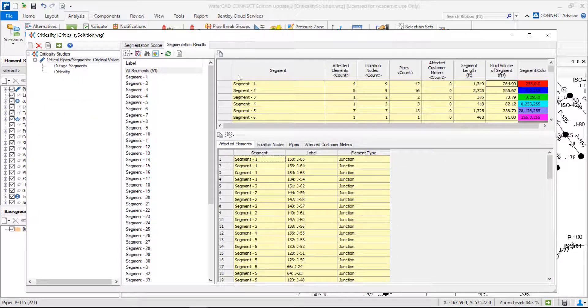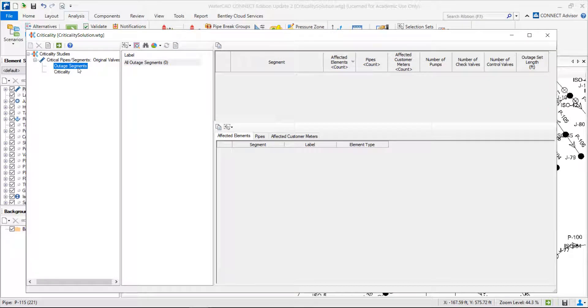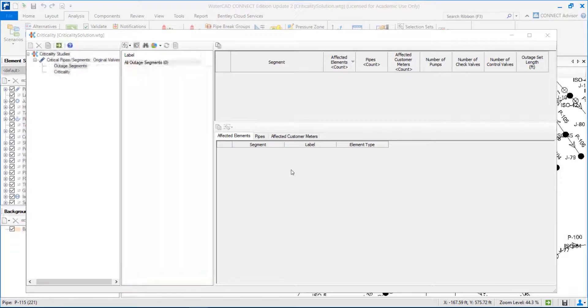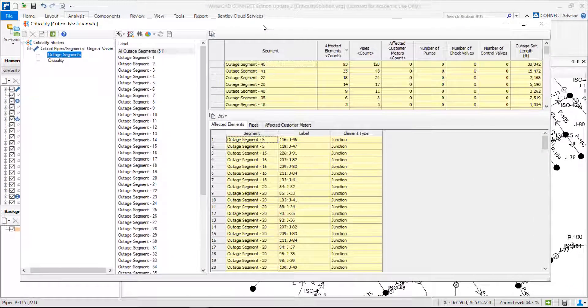Now let's go to the outage segments analysis. We just need to compute this. The outage segment analysis allows us to understand: if I have to close a specific segment, what is the impact downstream? Imagine I have to close this segment here — how many pipes will be affected downstream, how many pipes will be without water if I close this specific segment?